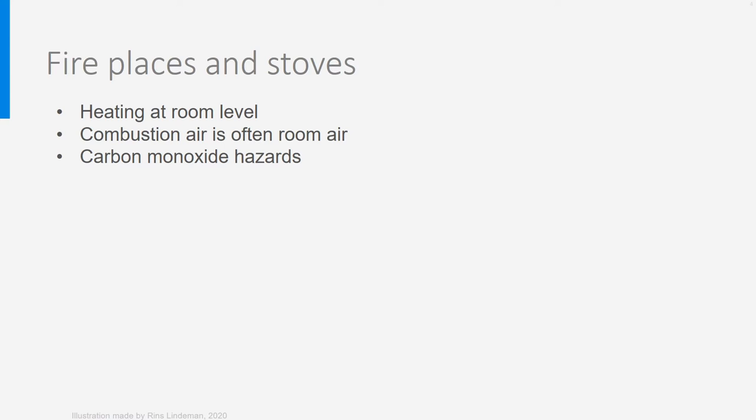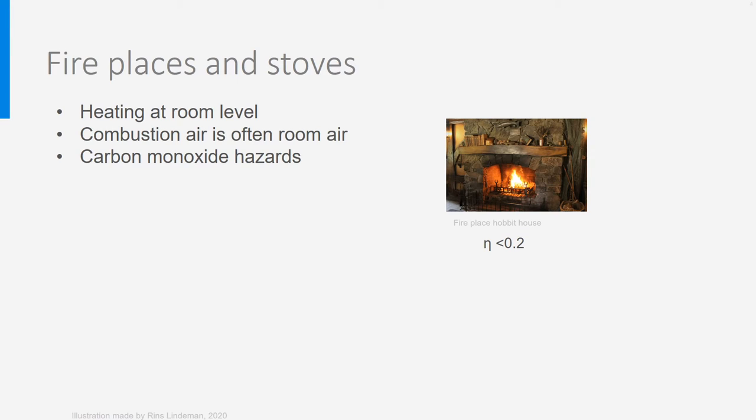Fireplaces and stoves are used for direct space heating at room level. Simple fireplaces, like the one on the picture, have a very low efficiency — less than 0.2 in general. Most heat is released with the exhaust gases through the chimney to the outdoor. Additionally, combustion gases, smoke and particulate matter may enter the room and result in poor indoor air quality.